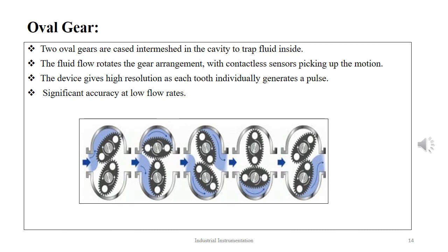The next type is the oval gear. Here, two oval gears are cased and intermeshed in the cavity to trap fluid inside. The fluid flow rotates the gear arrangement with contactless sensors picking up the motion. The device gives high resolution as each gear individually generates a pulse.